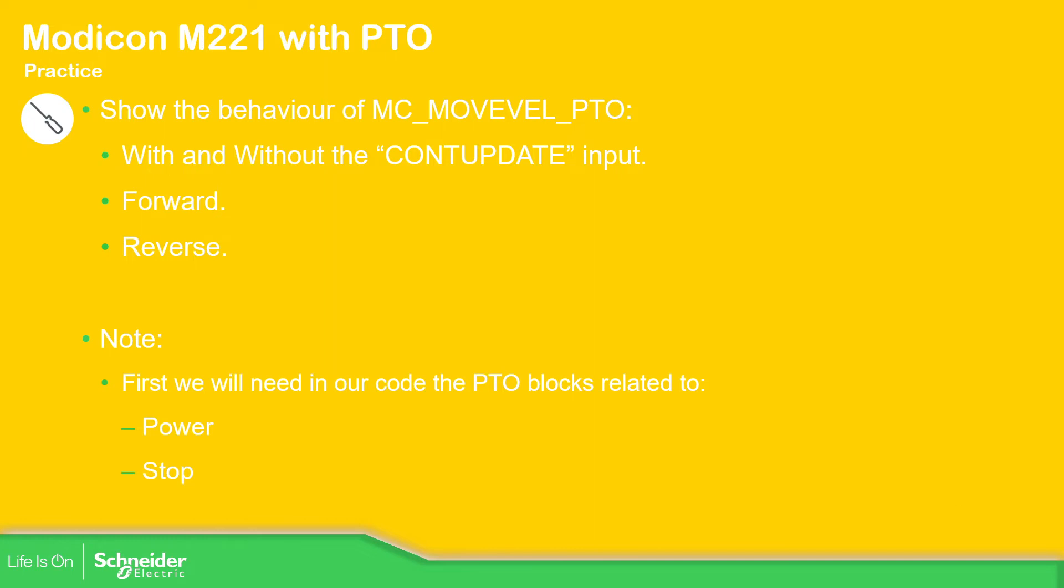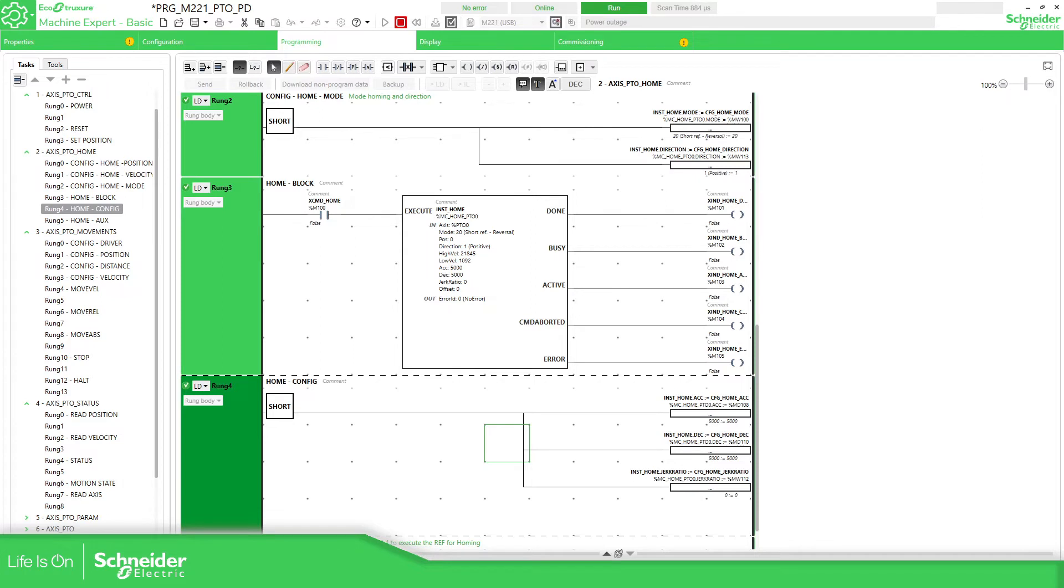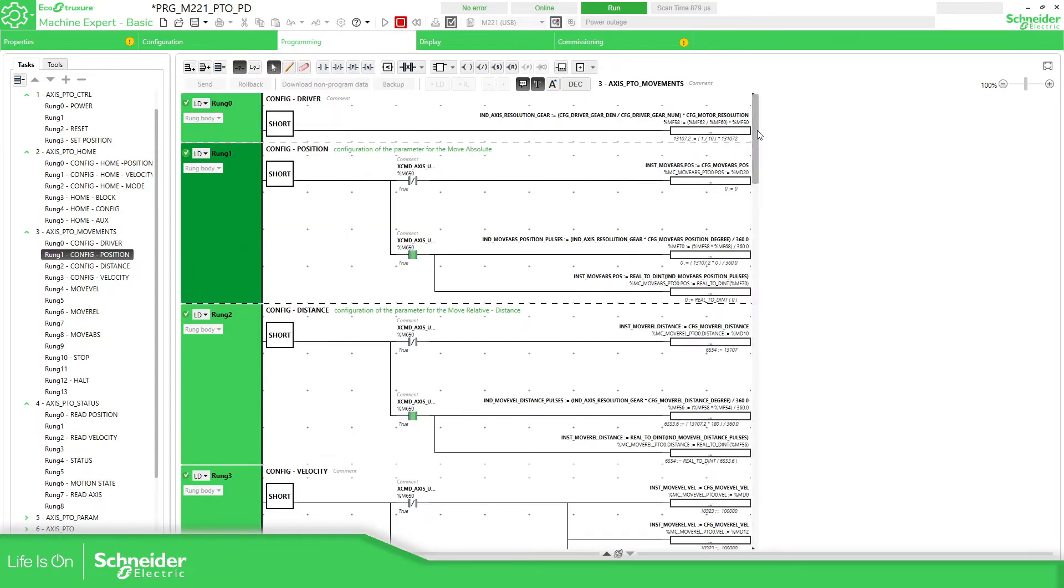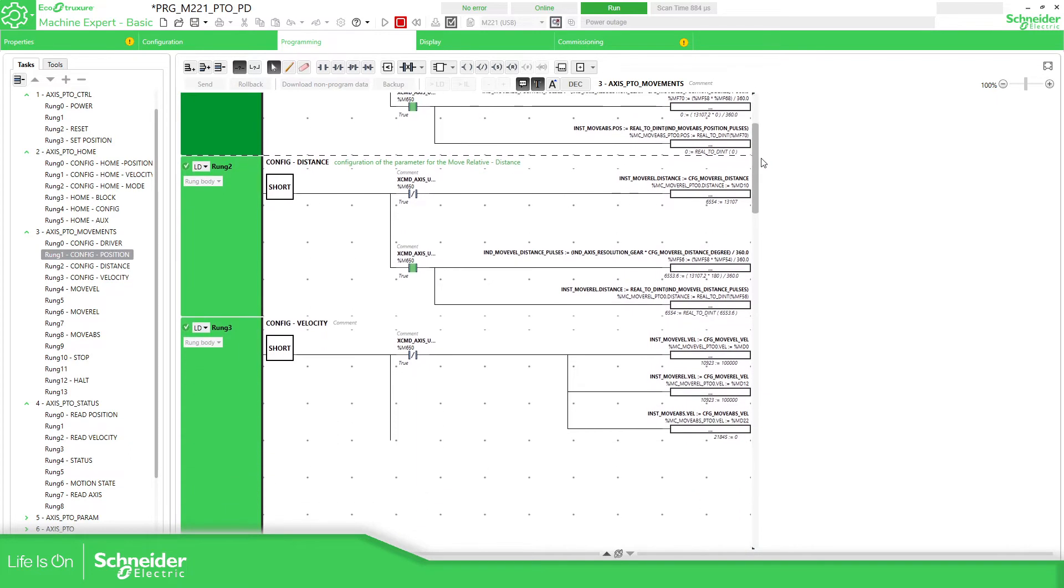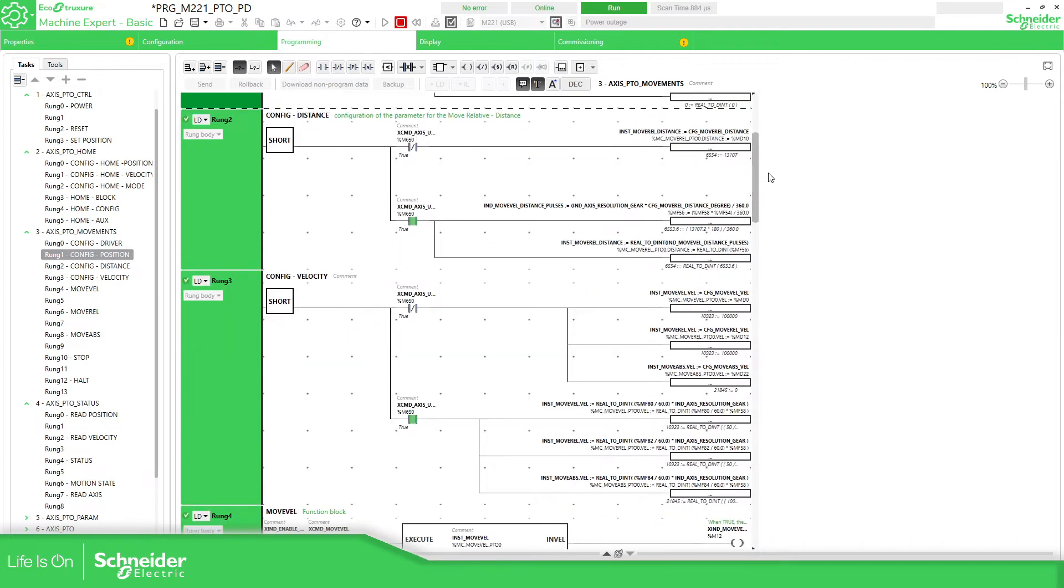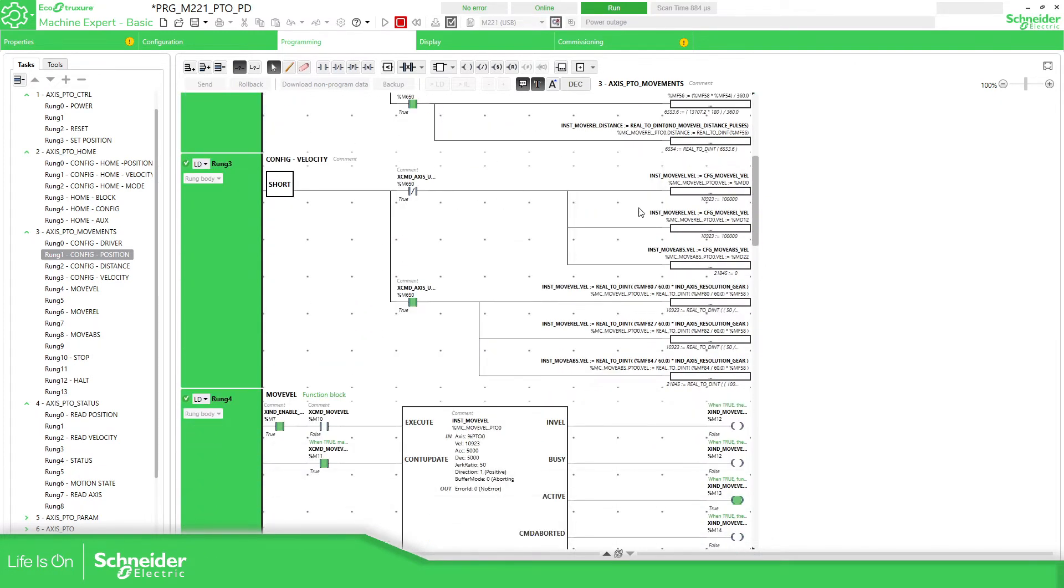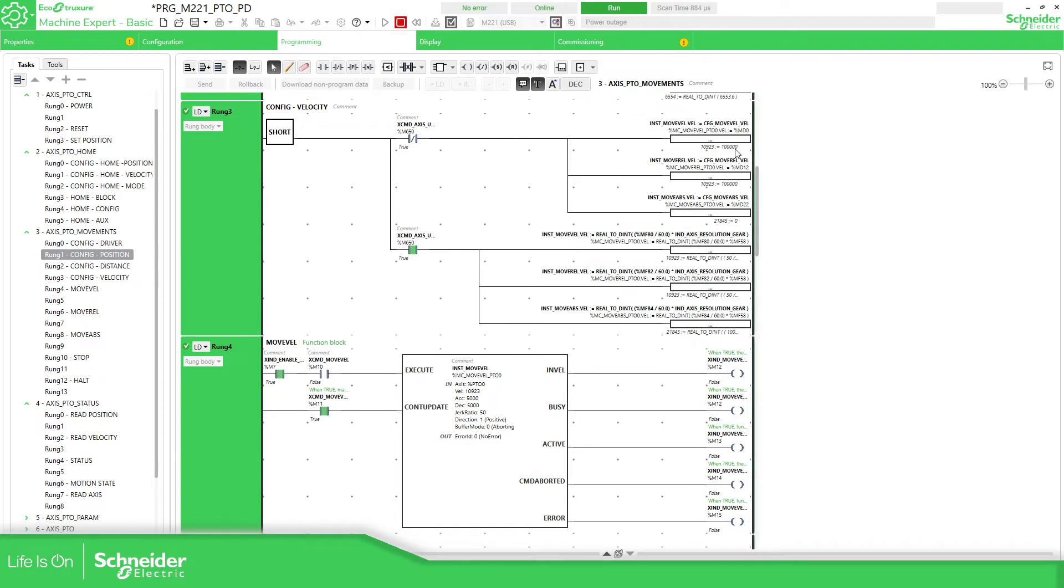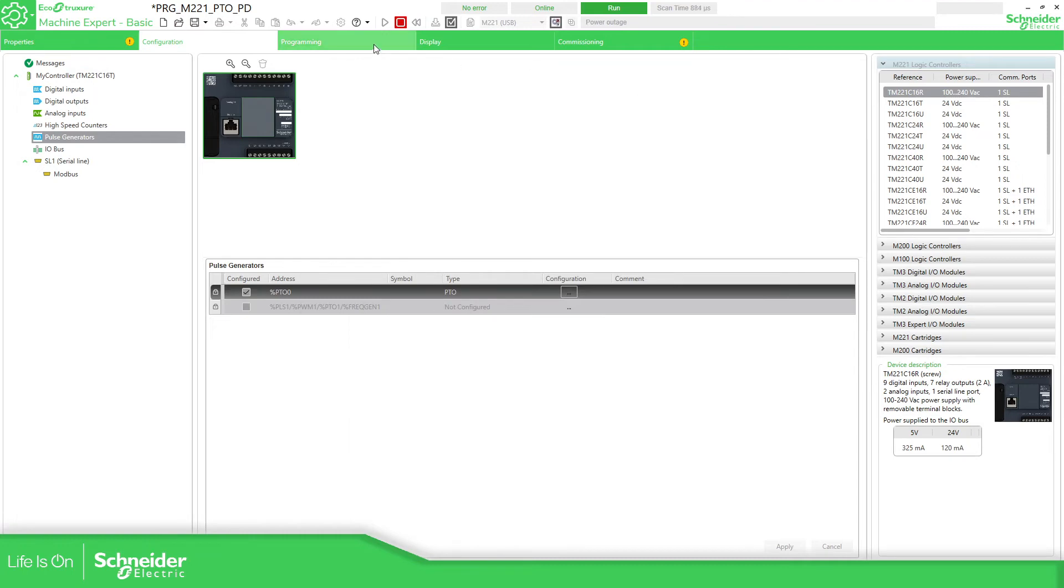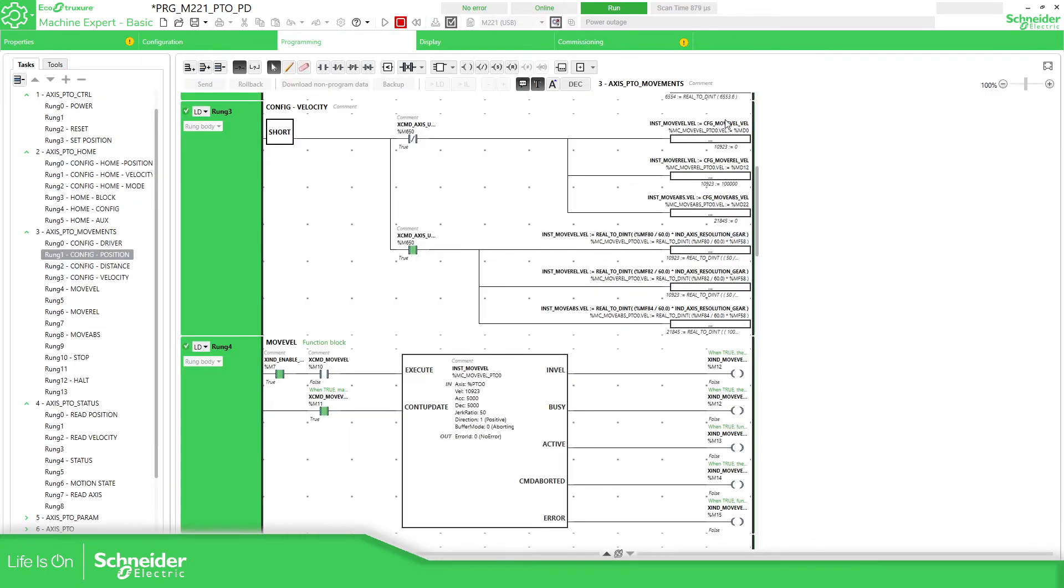So now this application is already connected to the controller. I have assigned the power. I have the power, so now it's enabled to make any movement that I want. So in my case, the only thing that we need to confirm in this case is if we want to go one direction, the other one and the velocity. So in the velocity, you will need to assign the frequency of the pulses that would be linked to this configuration that you already have. Remember that you have the 100 kilohertz for the max velocity. So you need to be careful in that.